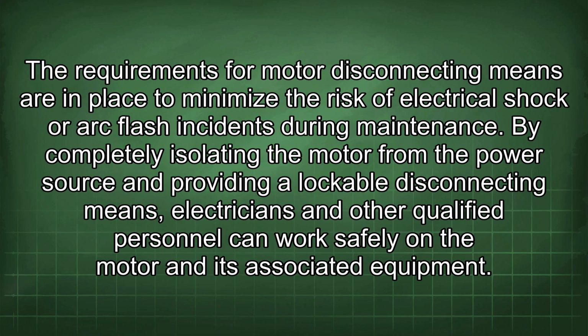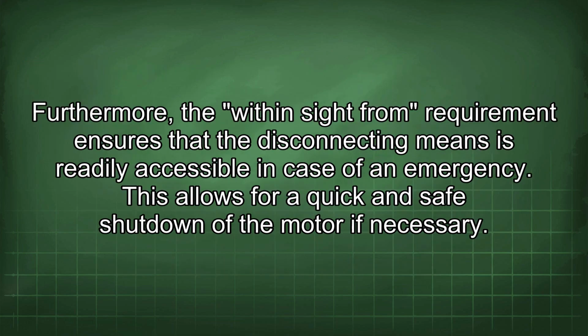The requirements for motor disconnecting means are in place to minimize the risk of electrical shock or arc flash incidents during maintenance. By completely isolating the motor from the power source and providing a lockable disconnecting means, electricians and other qualified personnel can work safely on the motor and its associated equipment. Furthermore, the within sight from requirement ensures that the disconnecting means is readily accessible in case of an emergency. This allows for a quick and safe shutdown of the motor if necessary.